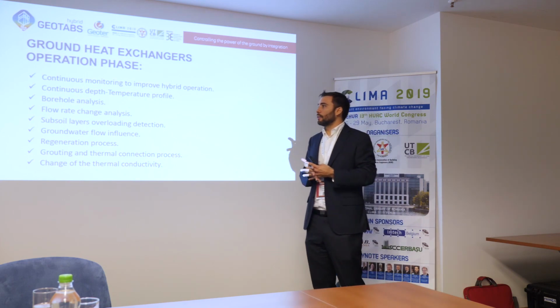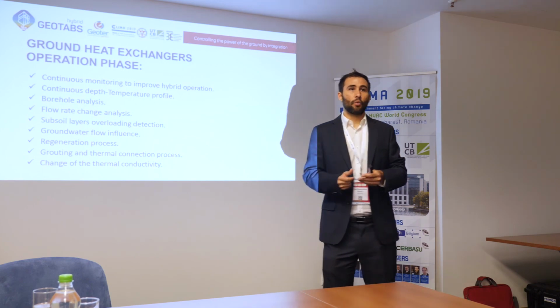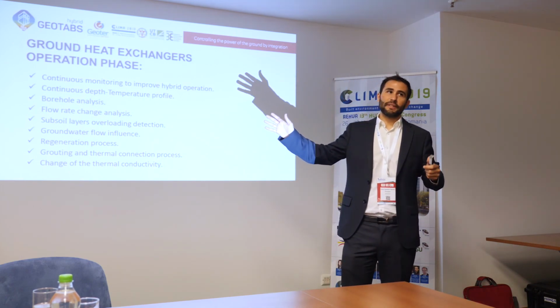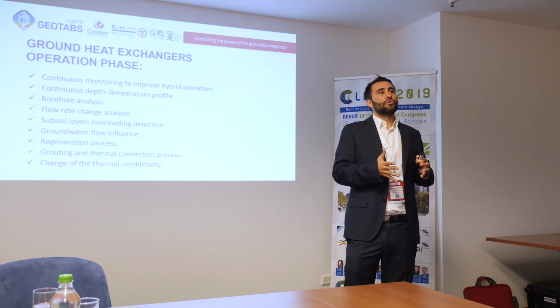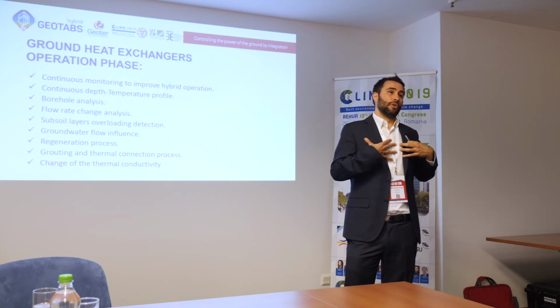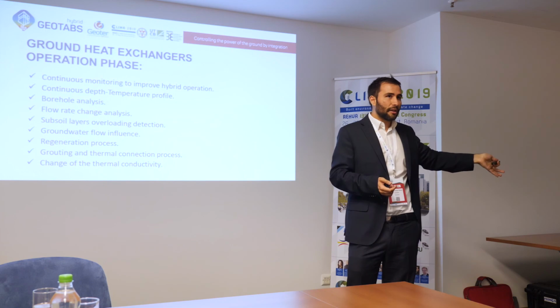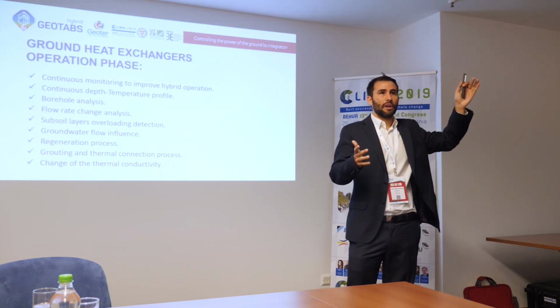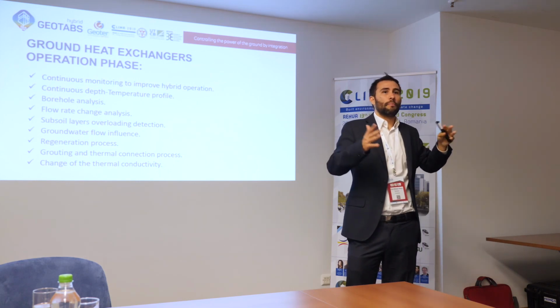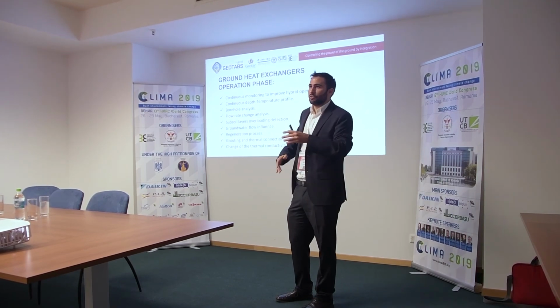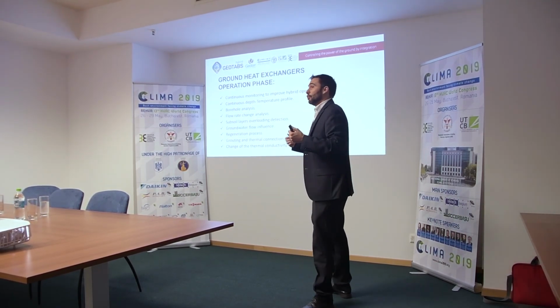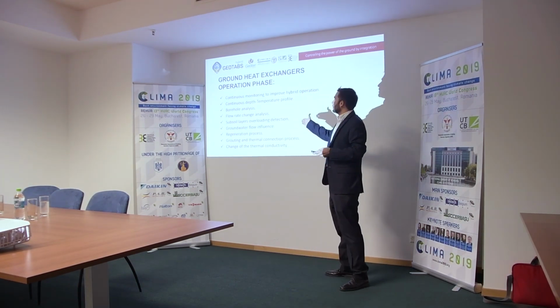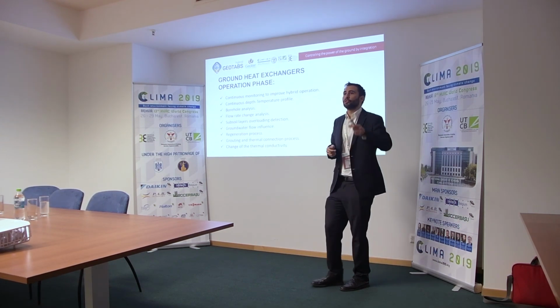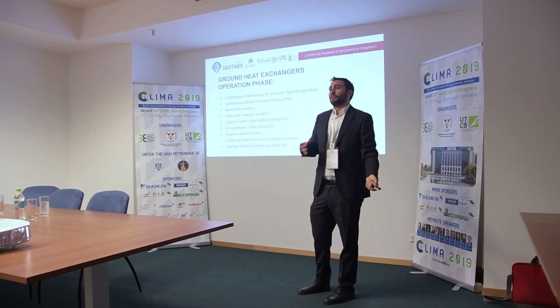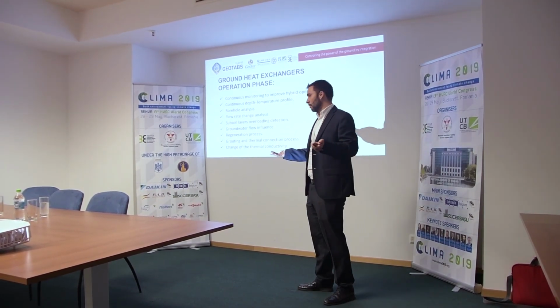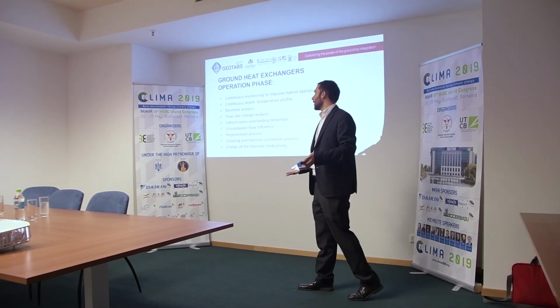Or, for example, as we are talking about hybrid GEOTABS buildings, taking into account the state of the borehole site, we can choose which energy source I want to use. Maybe it's interesting for me to use the geothermal heat pump or the air source heat pump, because of the different temperature conditions of the earth, or because the demand of the building changes, because the use of the building changes. So I need continuous operation information about the heat exchanger during the operation of the building. Only by introducing a fiber cable into the borehole, I can see this information. A fiber cable costs 2,000 or 3,000 euros. It's not very much.